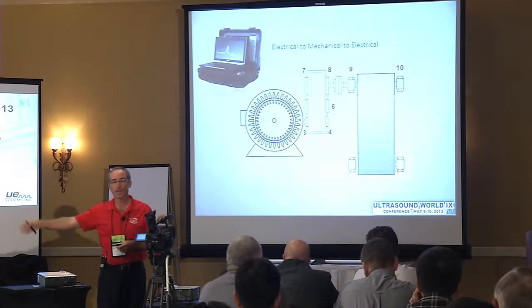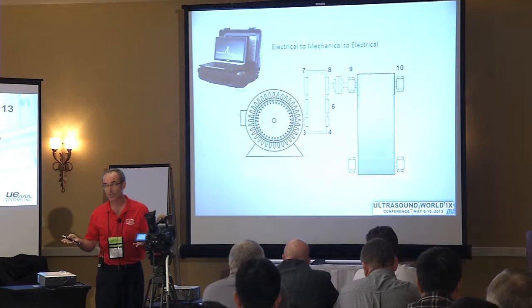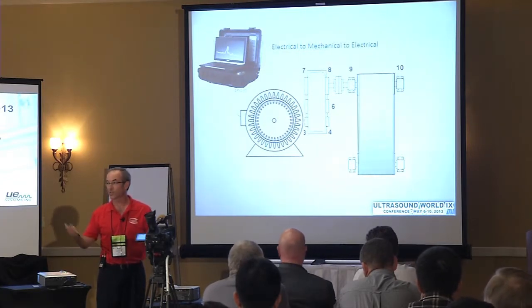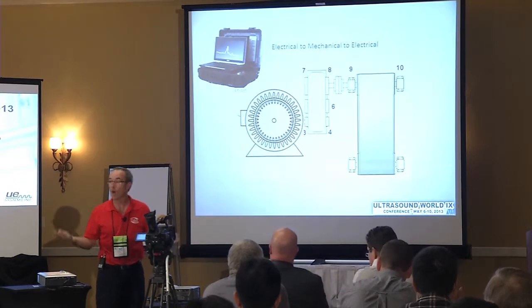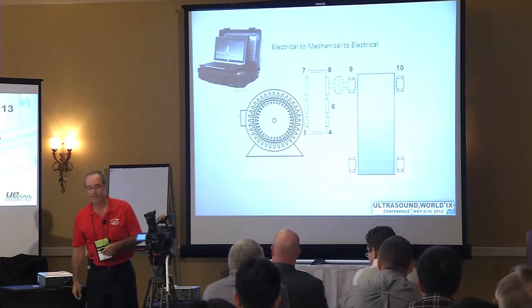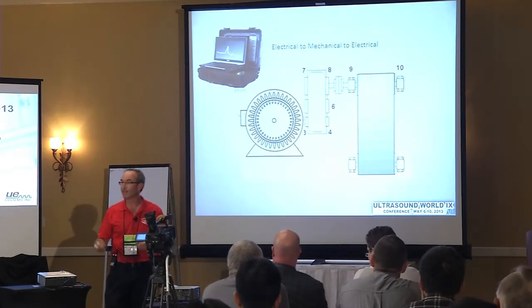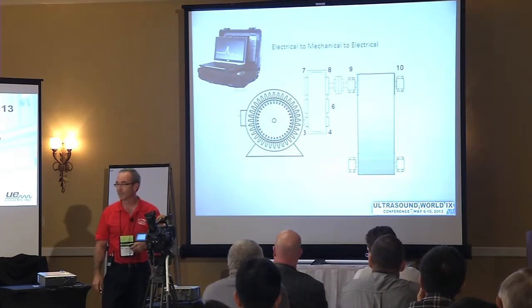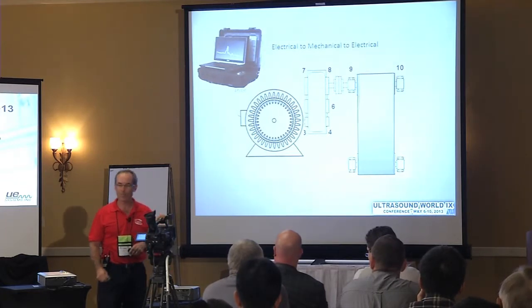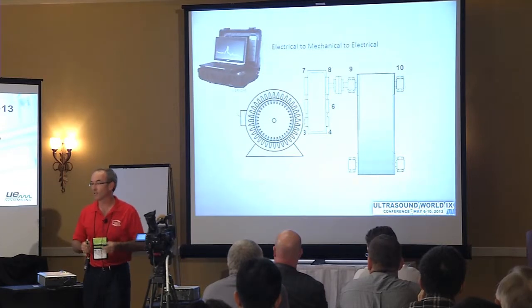Now, if you've got a motor hidden deep inside a reactor system that you can't get to, you'd like to know a stage 3 bearing failure is coming so you can start shutting the plant down a bit. It's coming, and we can tell when it's there—but by the time stage 3 arrives, you could hear it if you were standing next to it. So we're not going to be all about bearing analysis.